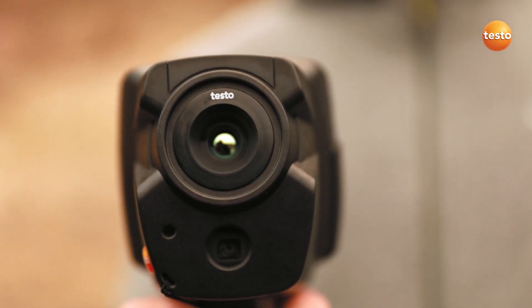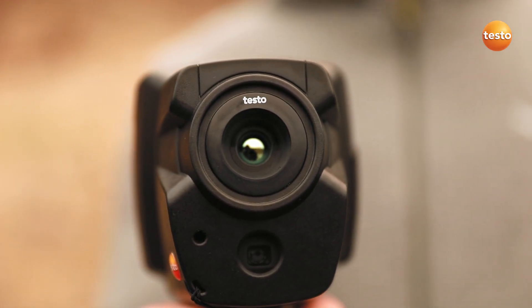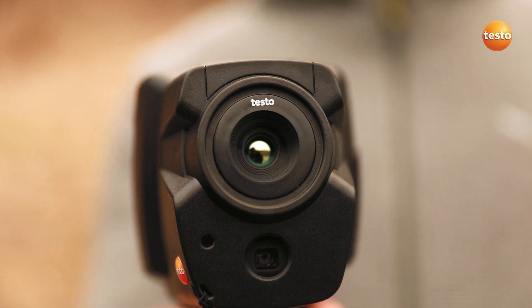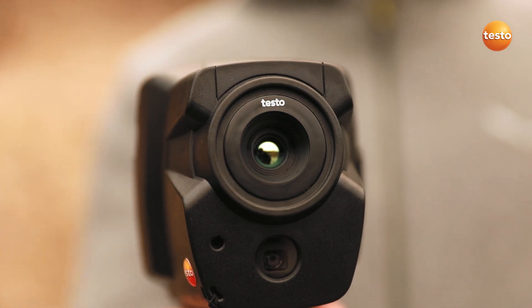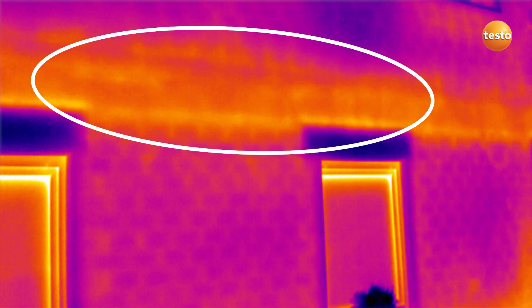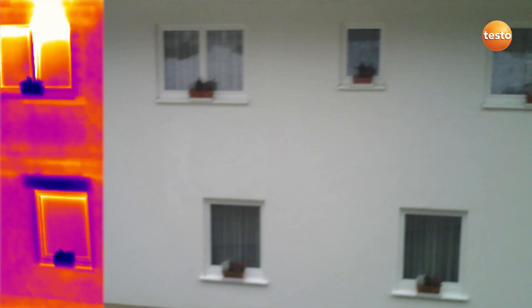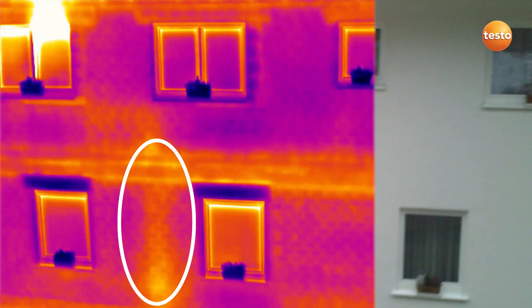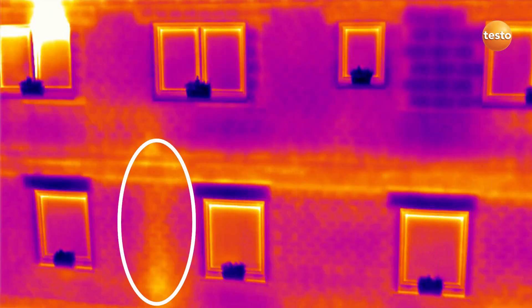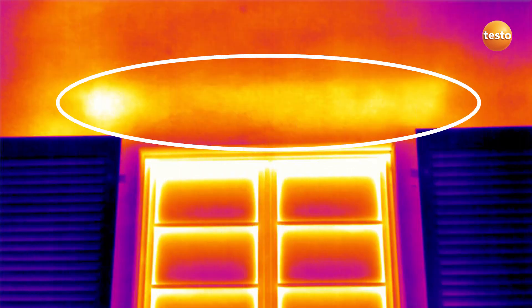Let's see which faults we can identify with the Testo 872 on the facade of this building: a cold bridge along the whole of the intermediate floor, the badly insulated riser of a radiator, and an unmistakable air leak at a window lintel.